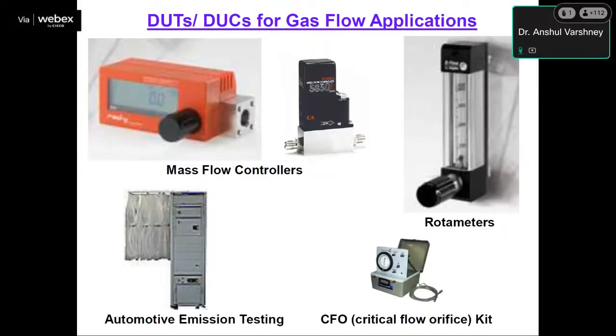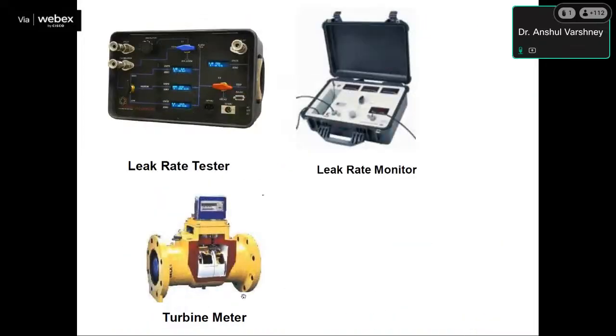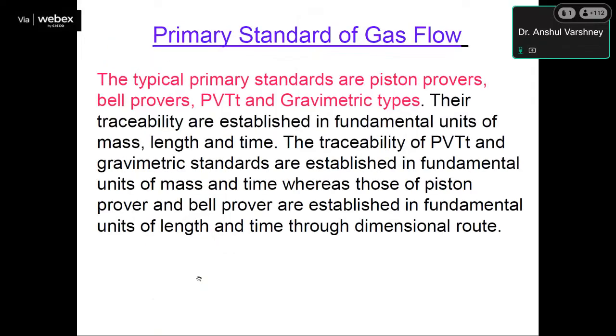So these are some devices under test used for gas flow systems, like mass flow controllers, rotameters, critical flow orifices, automotive emission testing, leak rate testers, leak rate monitors and turbine meters. The primary standards of gas flow systems are piston prover, bell prover, PVTT and gravimetric types. Their traceability is established in the fundamental units of mass, length and time. The traceability of PVTT and gravimetric standards is established in the fundamental units of mass and time, whereas that of piston prover and bell prover is established in the fundamental units of length and time.